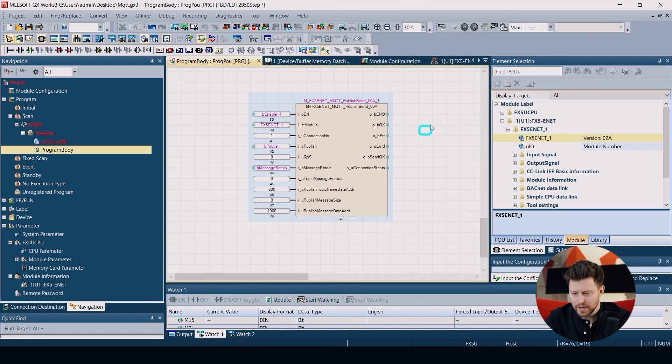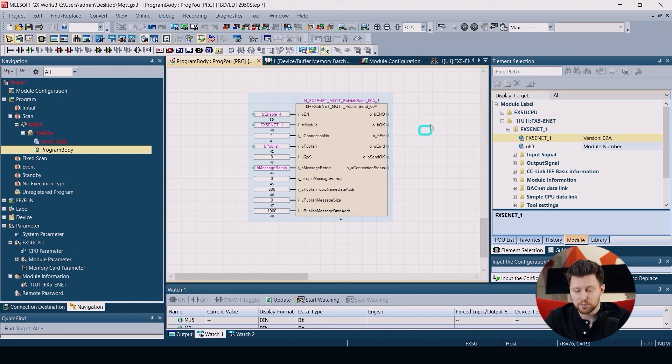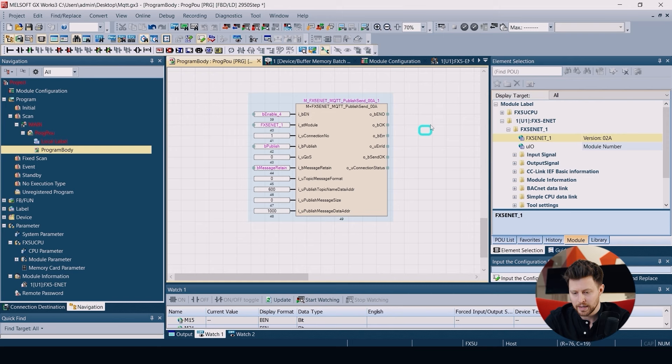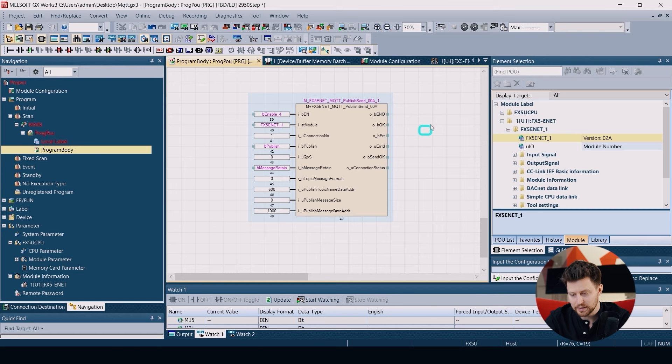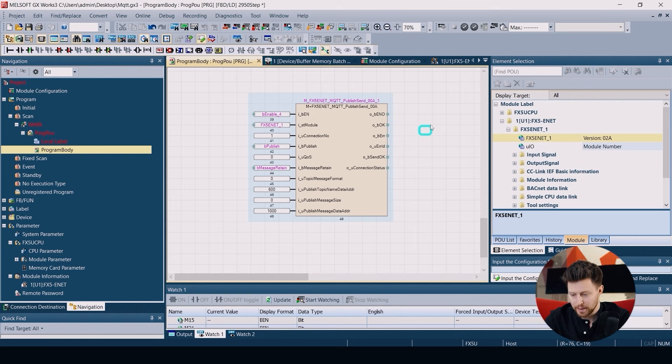We also have the message format and the starting register to store the topic name. In my case it will be the same topic that we used in the subscribe function block, so I put here the same register R600. Then we have the publish message size. When we put zero here, the size of message will be automatically calculated. And the last one is the starting register with the message to be published. I choose the register R1000.